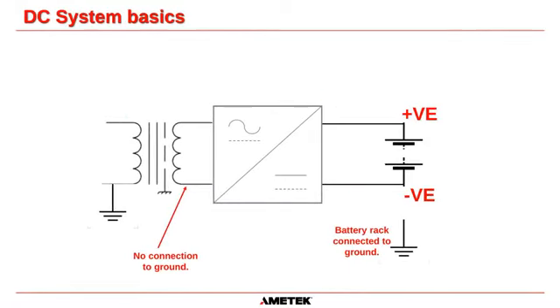So let's take it one step further now. That was just talking about the isolation transformer. So now we're going to add a rectifier or a charger to the system. This is exactly the same as what we had on the previous page. Remember, we now have no connection to ground in this system whatsoever. So when we convert that AC to DC, there isn't something magic in the AC to DC conversion that gives it some form of ground anywhere. That's just not possible. It just goes through either diodes or SCRs and converts the AC into DC. So therefore, the positive of the output, which is connected to a battery, and the negative of the output of the system, which is connected to a battery, have no reference to ground. None. In its most basic form, that is how a charger operates.